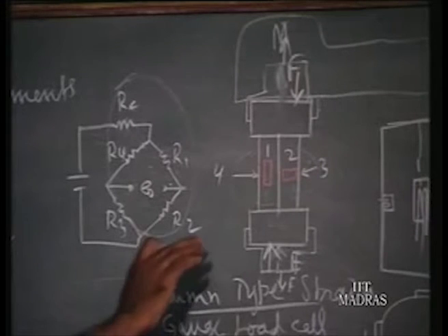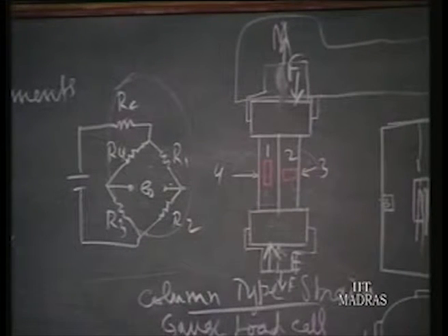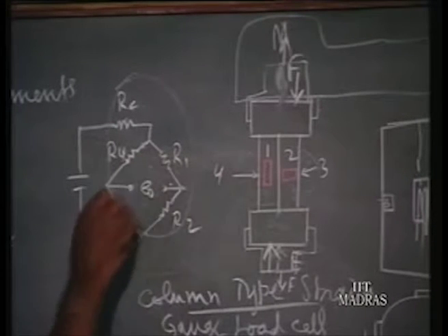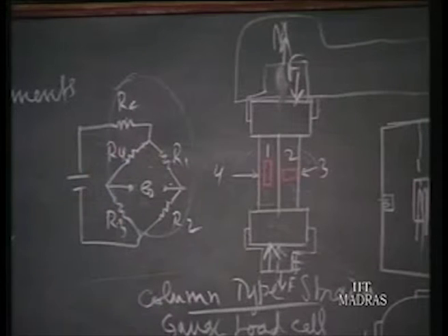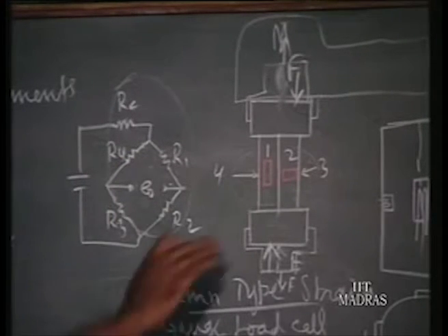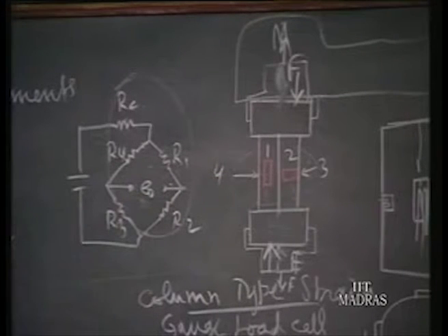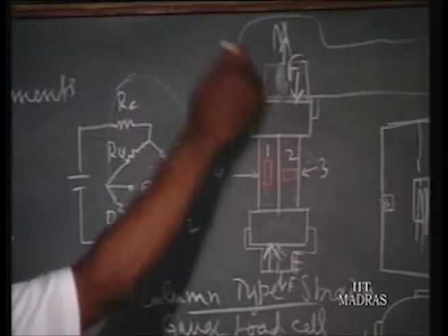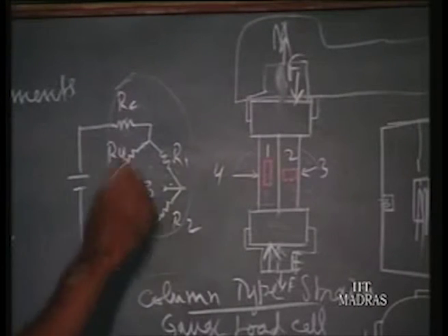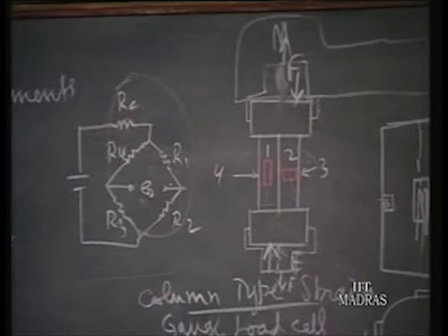Now 1 and 3 are subjected to opposite strains, which means they should be put in adjacent arms for maximum sensitivity. But you find they are put in opposite arms. So opposite strain in opposite arms gets nullified as per the rule of the bridge. So even if there is bending, there is no output due to that bending strain. Similarly, if eccentricity is in the other direction, 2 will be in tension and 4 in compression, and 2 and 4 are on opposite arms, so opposite strain gives rise to zero output voltage. So you will find this instrumentation is insensitive to both bending load and temperature effects.